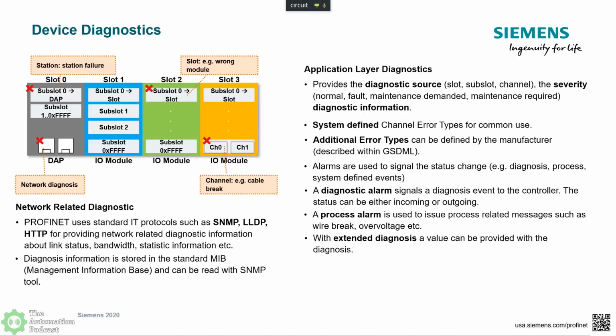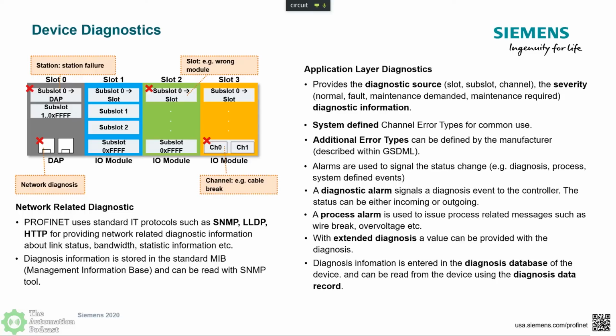The device vendor can also enrich the diagnostics information with some extended diagnosis. So that could be, in terms of an over voltage or over temperature, the temperature itself, so the value itself. That is the extended diagnosis of a device. And each diagnosis is stored in the diagnosis database of the I/O device and can be read by any PROFINET tool. It can be read by the I/O controller, but it can also be read by the I/O supervisor. Okay.